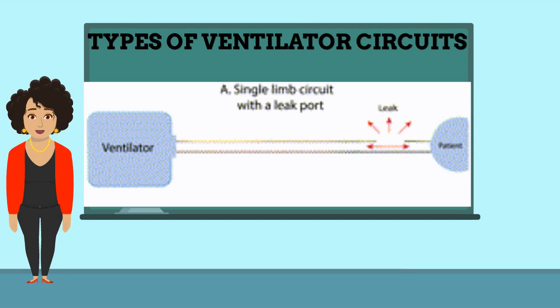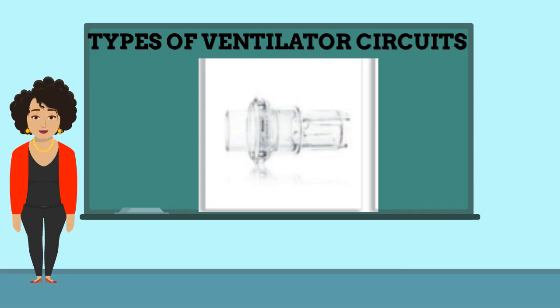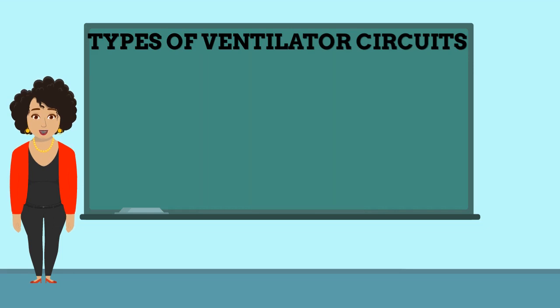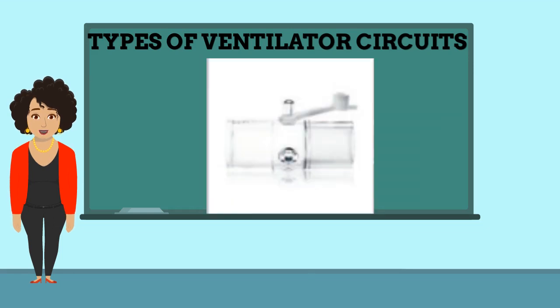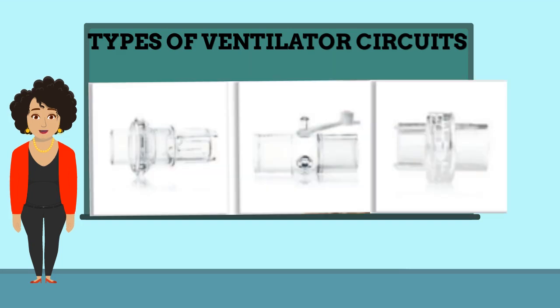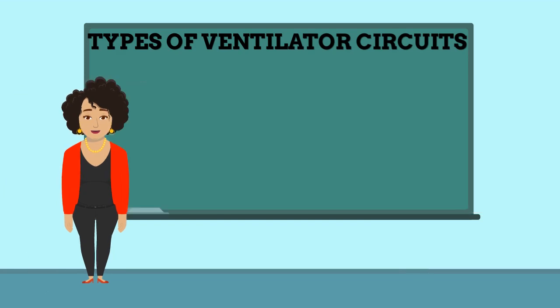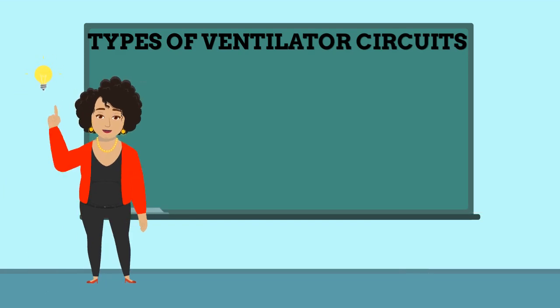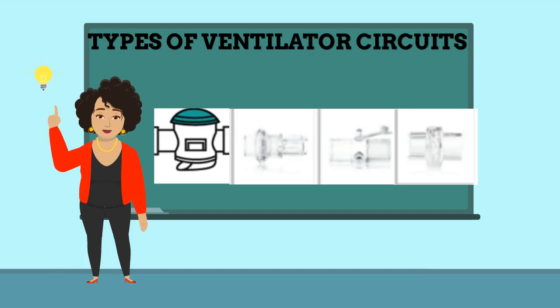A passive circuit has a calibrated intentional leak placed proximal to the patient. The whisper swivel, disposable swivel, and disposable fixed — all of these leak devices are exhalation ports. Now you know that an active or passive circuit has a type of exhalation port.